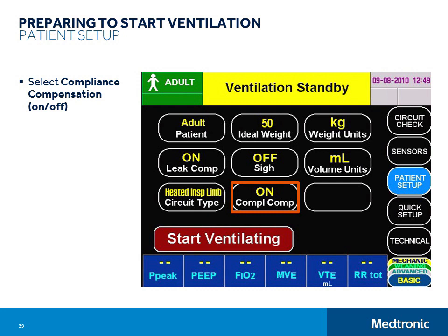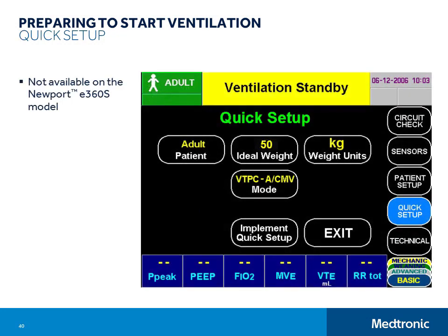The next menu item is the Quick Setup function. Quick Setup selects default ventilation and alarm parameter settings based on your entry of the patient's ideal body weight and mode and breath type preference. Using Quick Setup is a great way for less experienced caregivers to select safe new patient startup settings and for all caregivers to speed up the setup process. The Quick Setup function is only available while in standby.